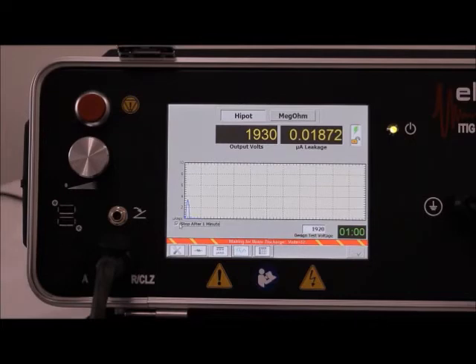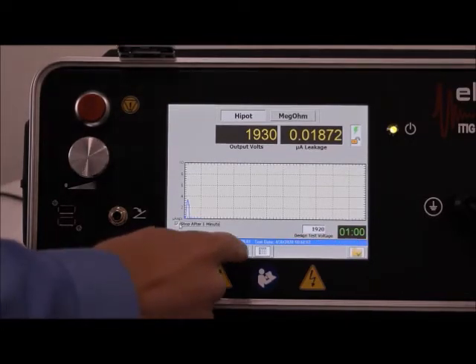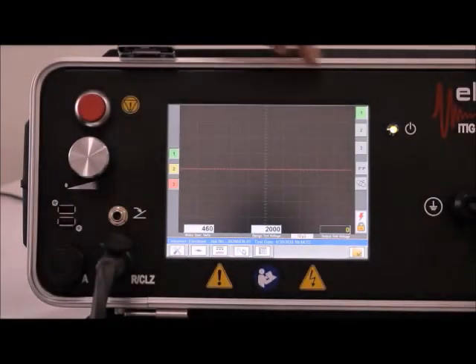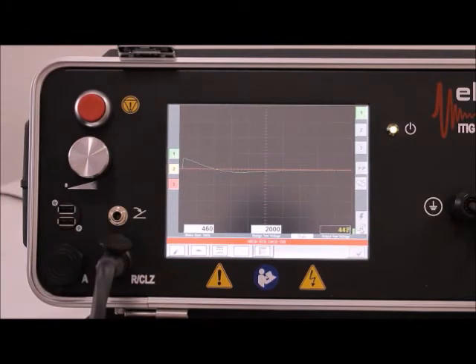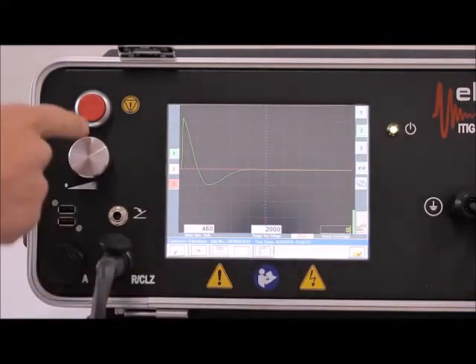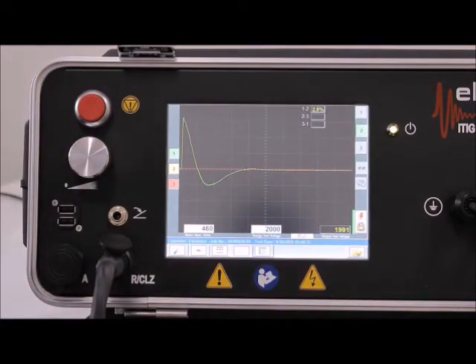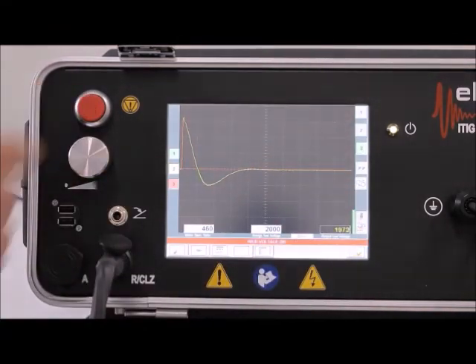And we're done discharging the windings. Hipot test is completed. Final step, surge test. Phase 1 is indicated. Arm the instrument, press the red button. The instrument automatically sets the time base and voltage scale. We're done with the surge test in phase 1. Select phase 2, arm the instrument, press red button. Phase 2 is done, similar to phase 3.